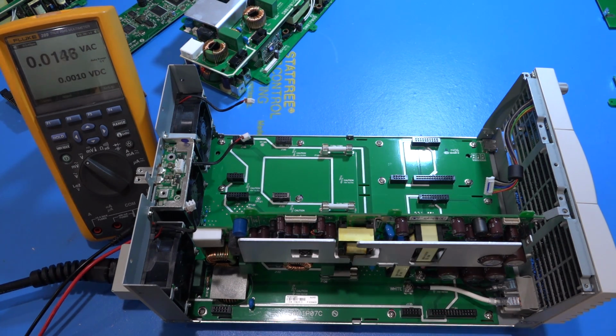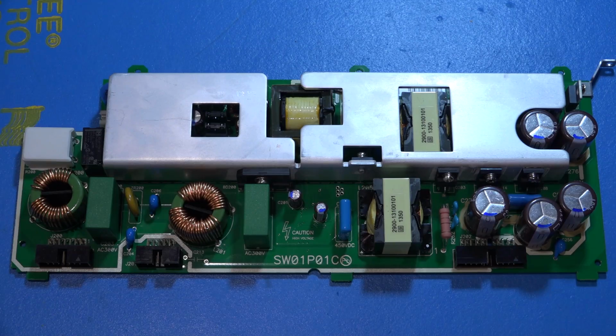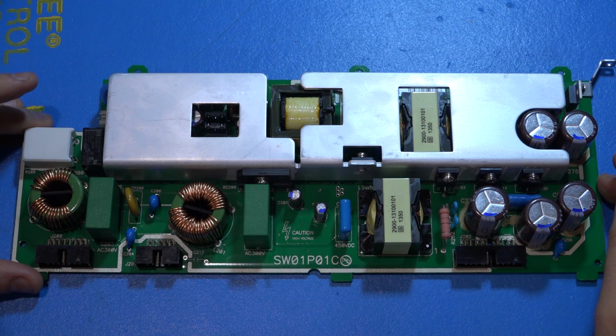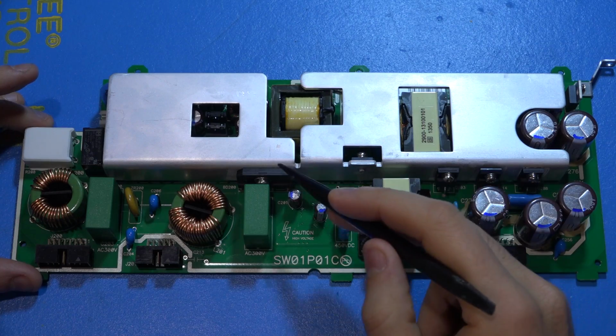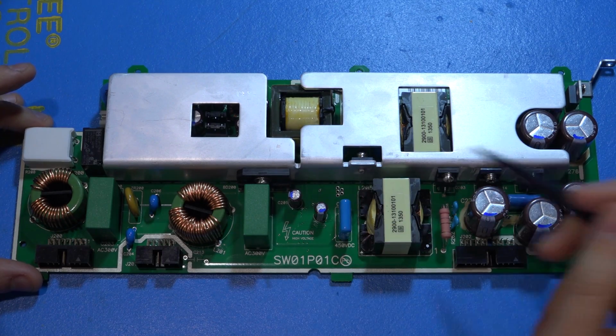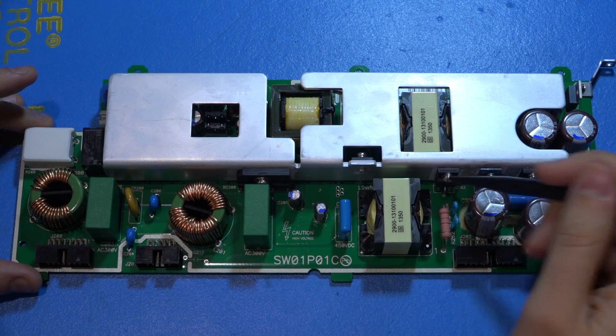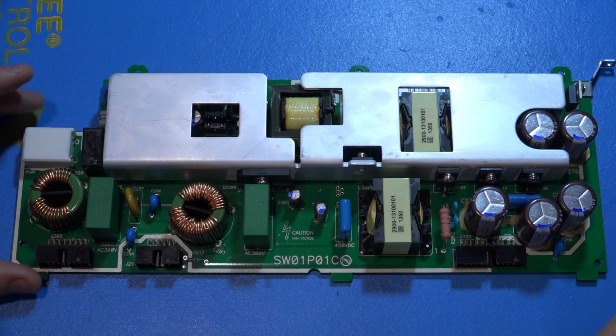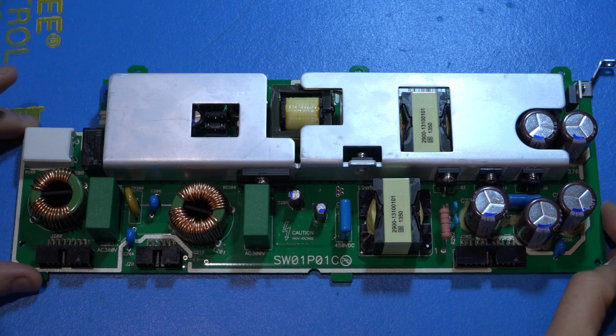Let's go ahead and take a look at this a little bit closer by itself under the camera, so we can do some reverse engineering and figure out what's wrong with it. So here's the unit that doesn't go through the soft start. I looked at it, it doesn't seem to have any mechanical damage or obvious burn marks. I checked the rectifier, it's correct, it has all the diodes properly. I checked these devices here, they all seem fine, but somehow the relay doesn't start.